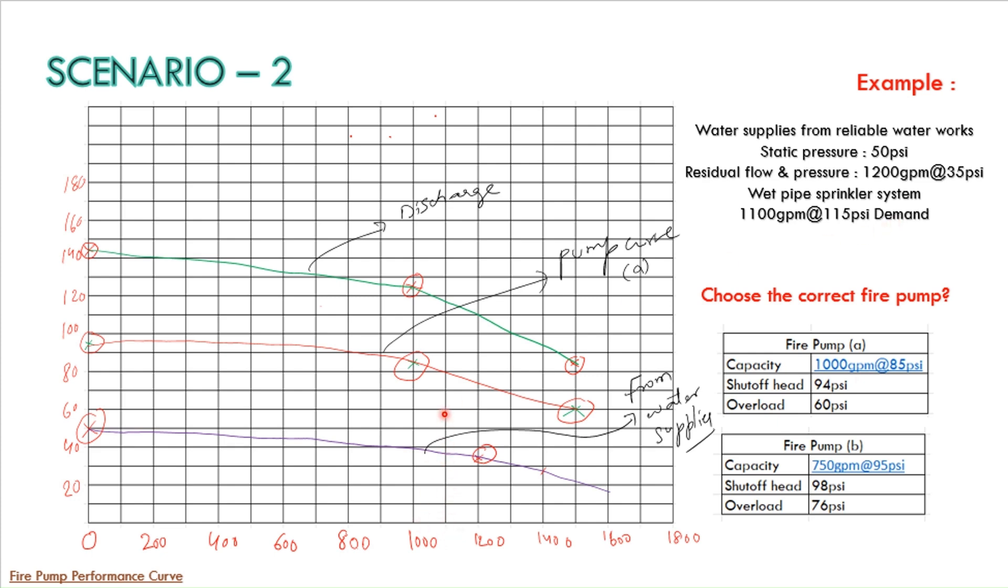So I will just mark here. So it will be here. So this particular thing is below the discharge curve or discharge line.